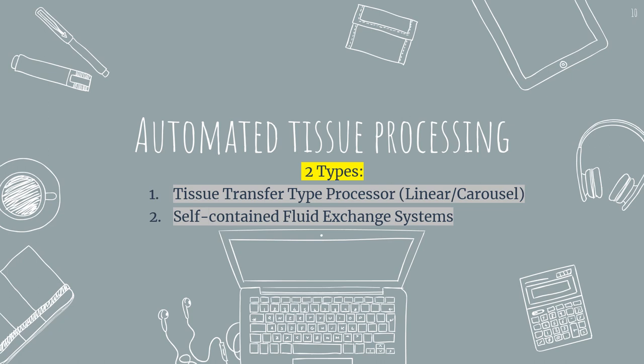There are two types of automated tissue processing. First is the tissue transfer type processor — linear or carousel. Second is the self-contained fluid exchange system. The basic principle for tissue processing requires the exchange of fluids using a series of solutions for a predetermined length of time in a controlled environment. In the machine, it is electronically timed and then fluids are exchanged.